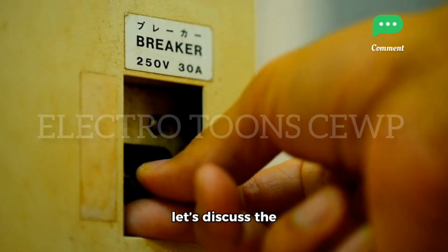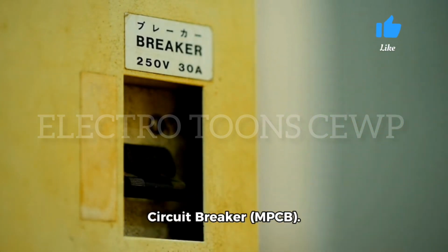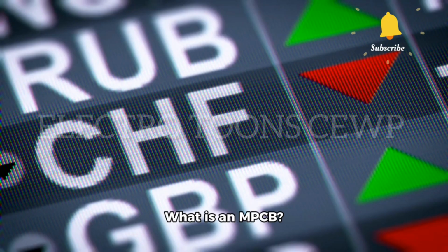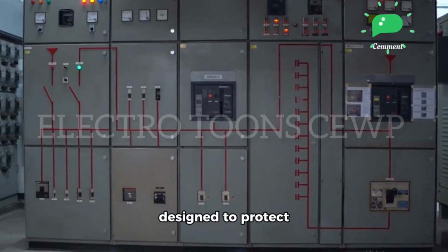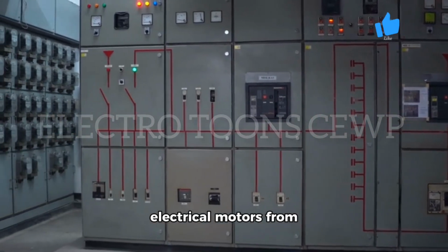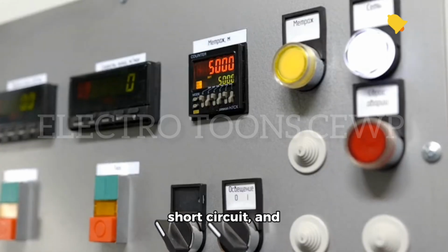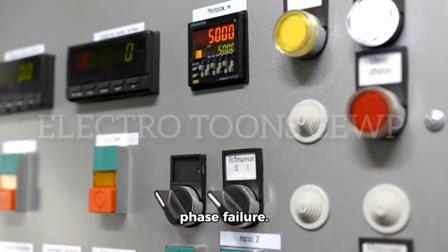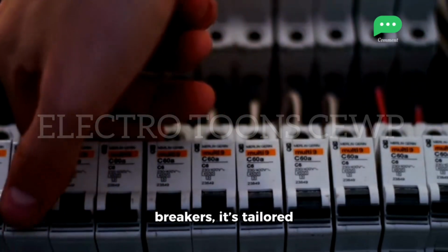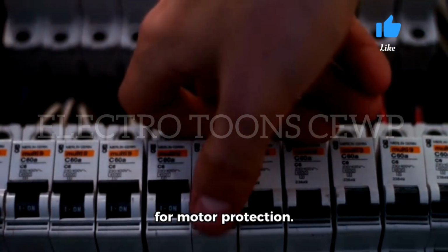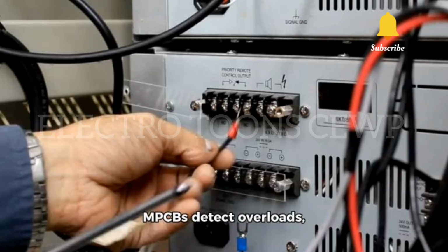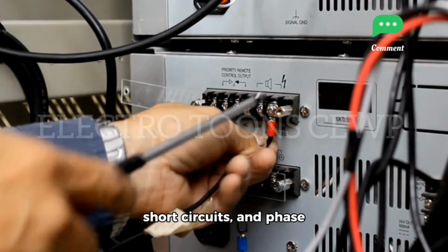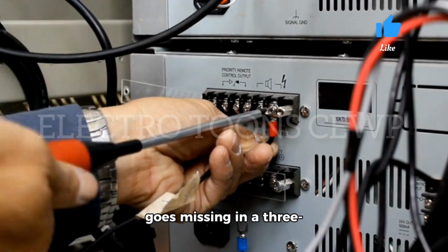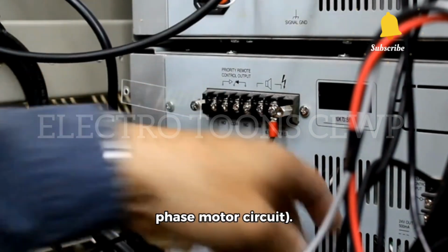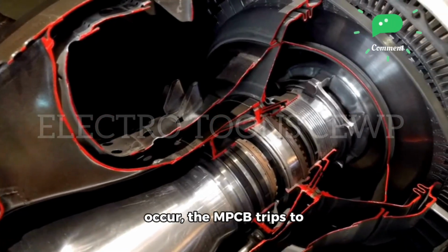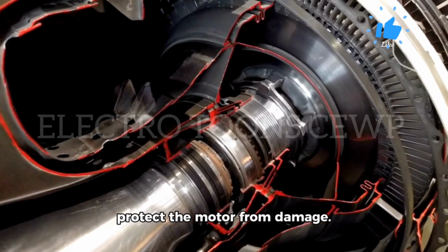MPCB, motor protection circuit breaker. Finally, let's discuss the motor protection circuit breaker, MPCB. What is an MPCB? An MPCB is specifically designed to protect electrical motors from damage due to overload, short circuit, and phase failure. Unlike regular circuit breakers, it's tailored for motor protection. How does an MPCB work? MPCBs detect overloads, short circuits, and phase failure, when one phase goes missing in a three-phase motor circuit. When any of these faults occur, the MPCB trips to protect the motor from damage.